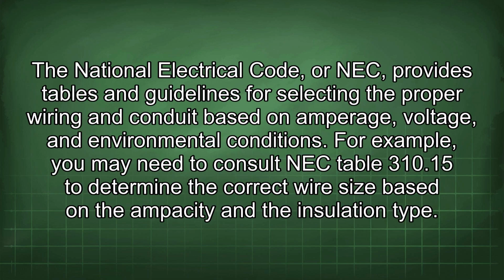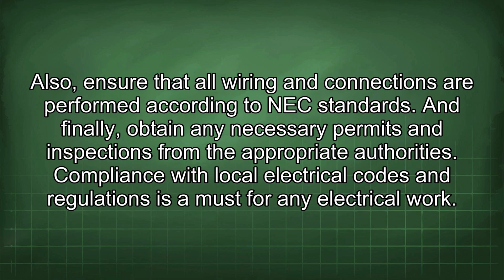The National Electrical Code, or NEC, provides tables and guidelines for selecting the proper wiring and conduit based on amperage, voltage, and environmental conditions. For example, you may need to consult NEC Table 310.15 to determine the correct wire size based on the ampacity and the insulation type. Also, ensure that all wiring and connections are performed according to NEC standards. And finally, obtain any necessary permits and inspections from the appropriate authorities. Compliance with local electrical codes and regulations is a must for any electrical work.